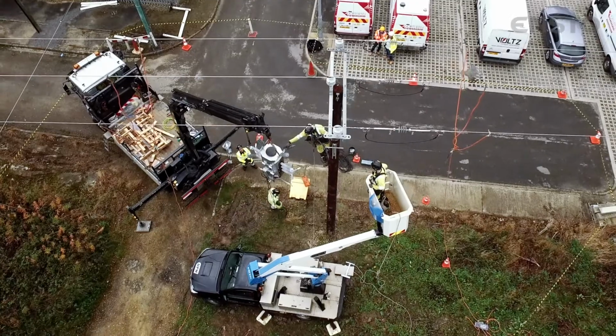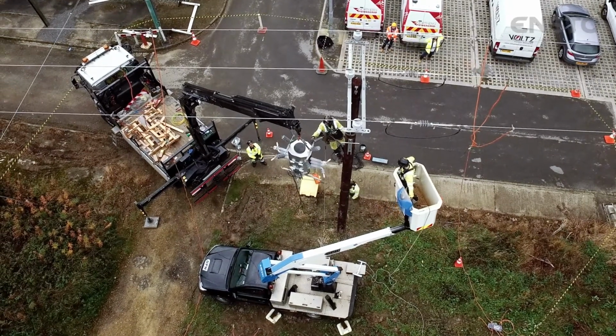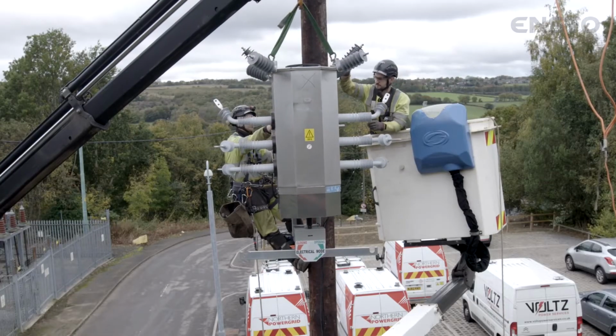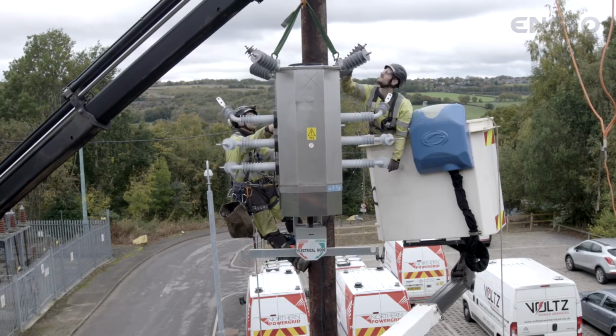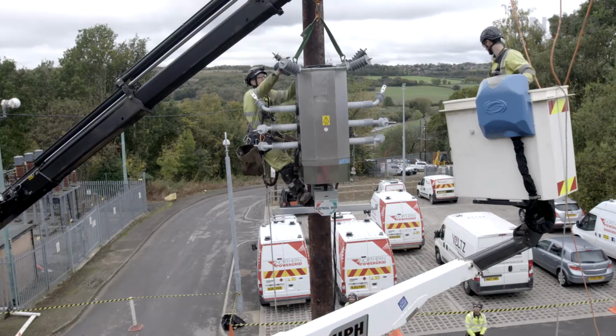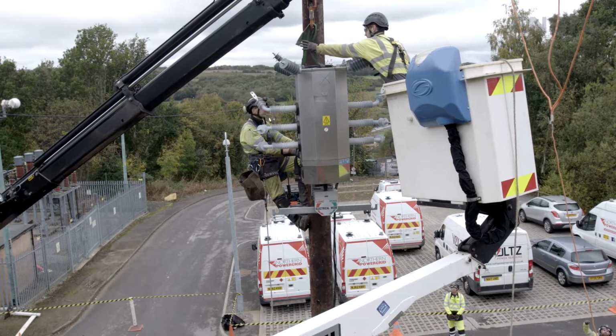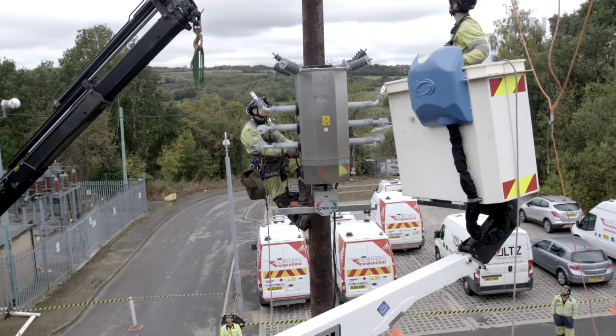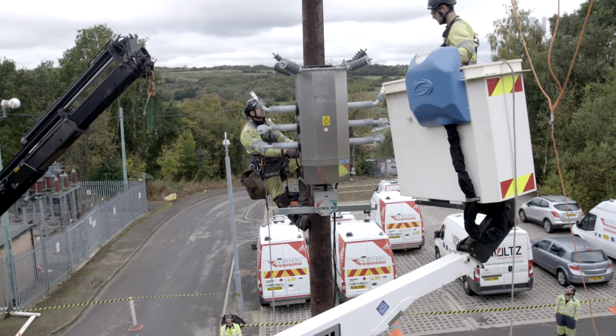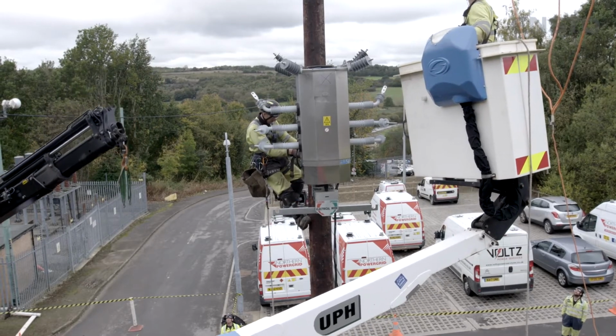Using the HIAB, raise the switch and carefully locate onto the mounting bracket. Then, slowly lower the HIAB jib to ensure the switch is located correctly. Confirm, and then remove the slings from the lifting points. At this stage, adjust the guide onto the pole and tighten.